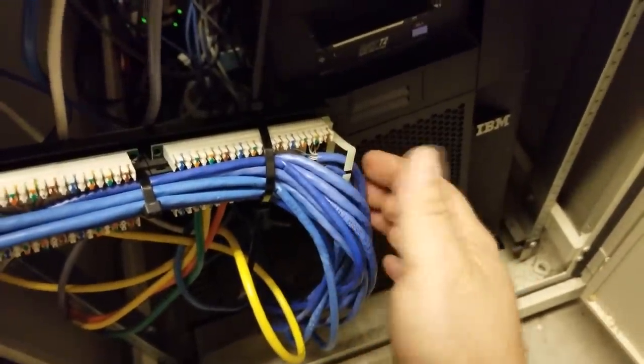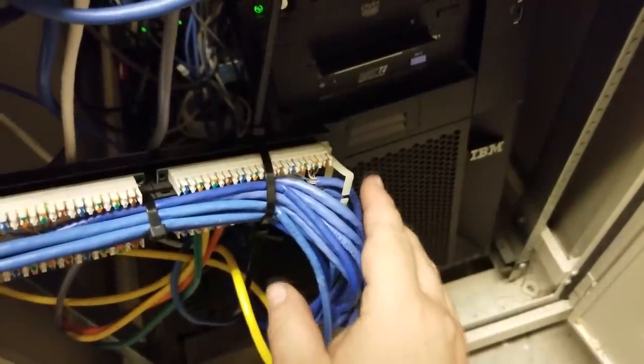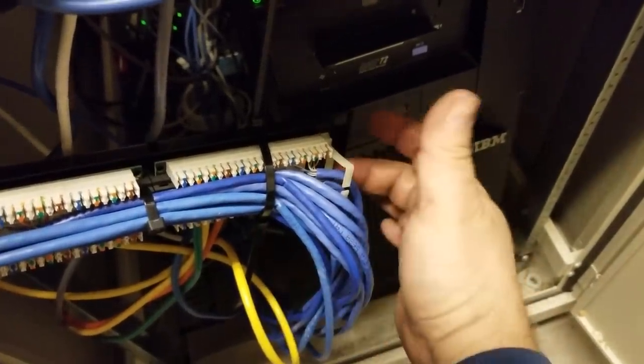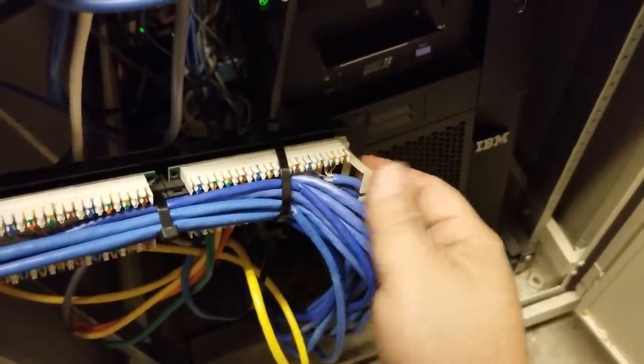I much prefer patch cables coming straight back from the panel and doing everything in that orientation rather than laying them flat like this. I found this out the hard way on a job where I had a problem with a line after assembling like 200 drops and realized it was buried underneath — luckily I was able to fix it without too much destruction. That's why I don't do this anymore.